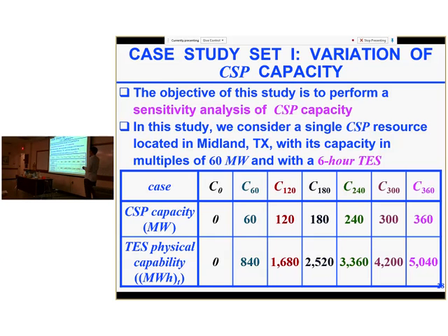For the example here, for a 6-hour thermal energy storage, if the storage is full, it will store 840 megawatt hours of thermal energy, and in each hour, the power block can withdraw at most 140 megawatt hours of thermal energy to generate 60 megawatt hours of energy in 1 hour.